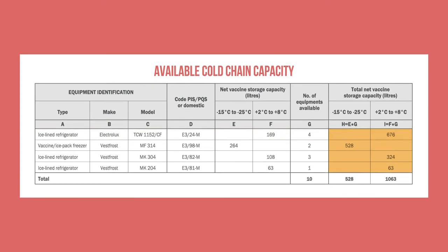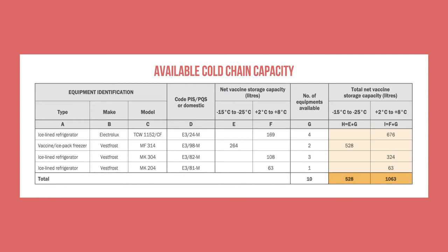There are four of this type of refrigerator, holding a total net volume of 676 litres. For each type of equipment, record the total net vaccine storage capacity in the appropriate temperature range column. Once you have done this for each type of equipment, add the volumes together for each temperature category. In this case, there is a total freezer capacity of 528 litres and a refrigerator capacity of 1,063 litres spread over 10 pieces of equipment.